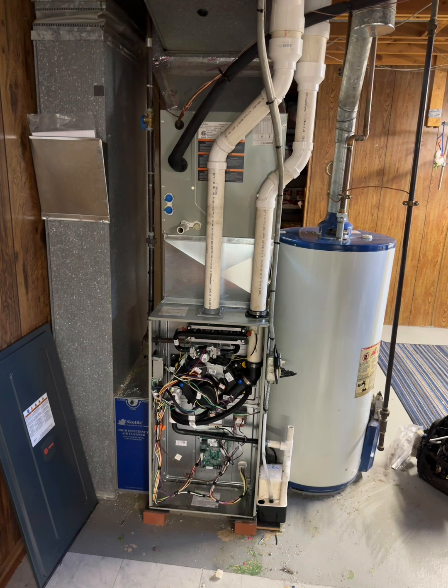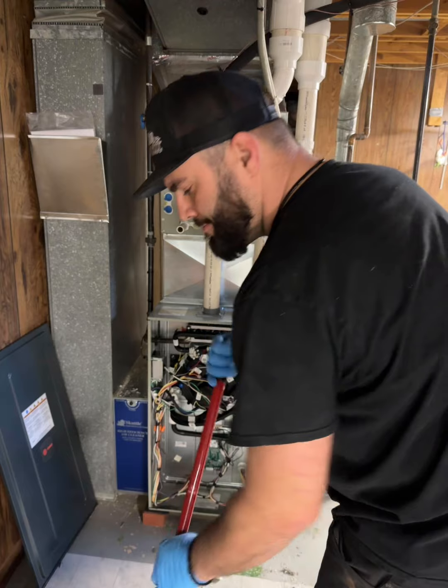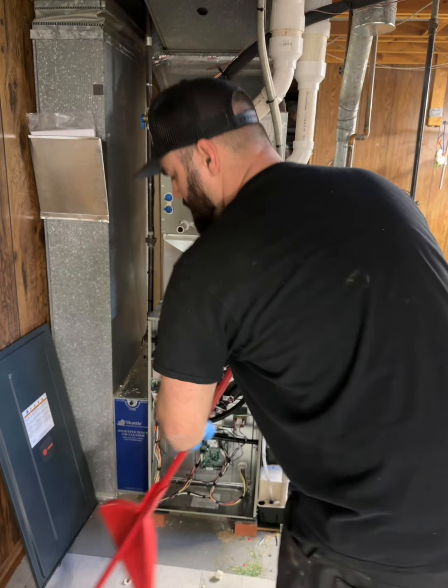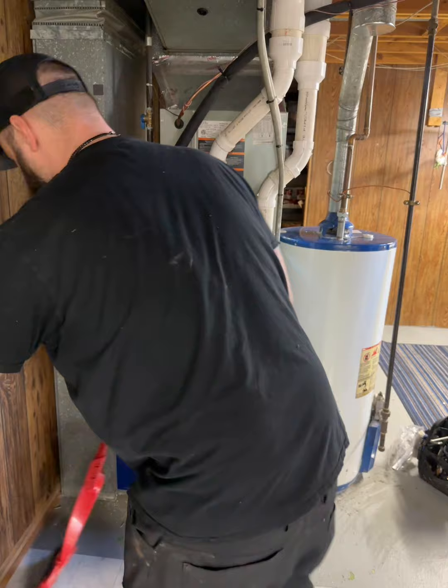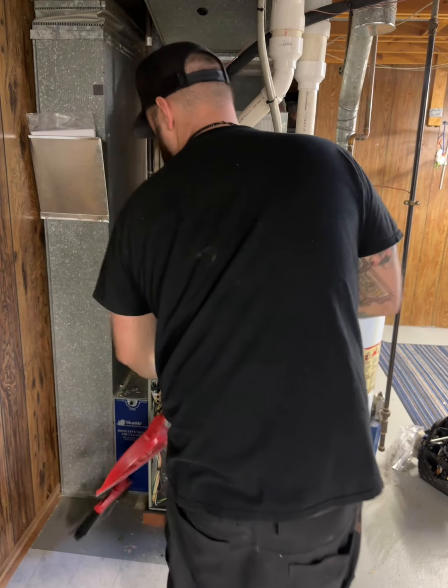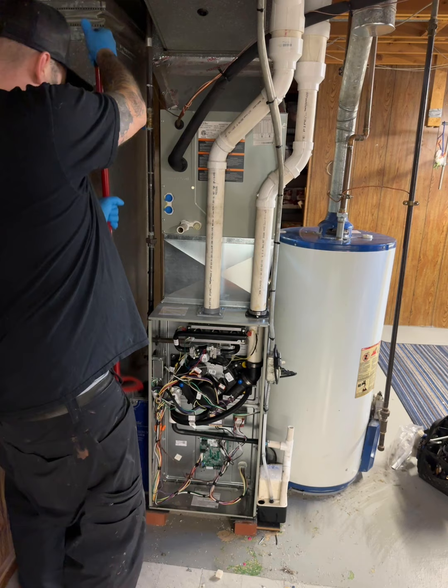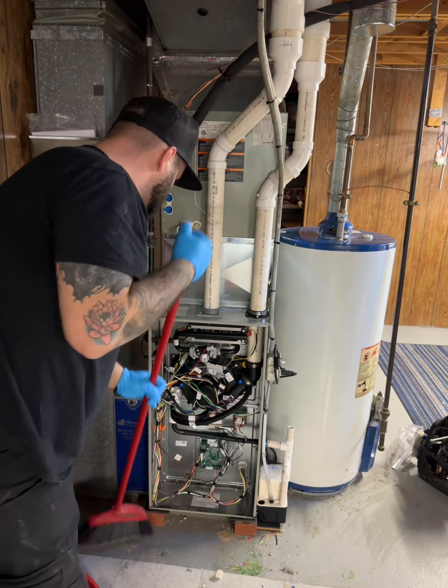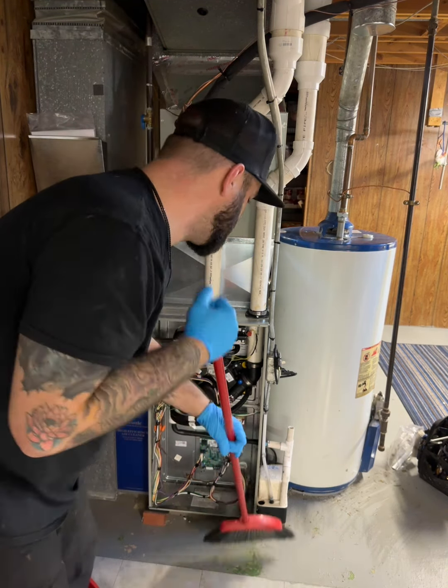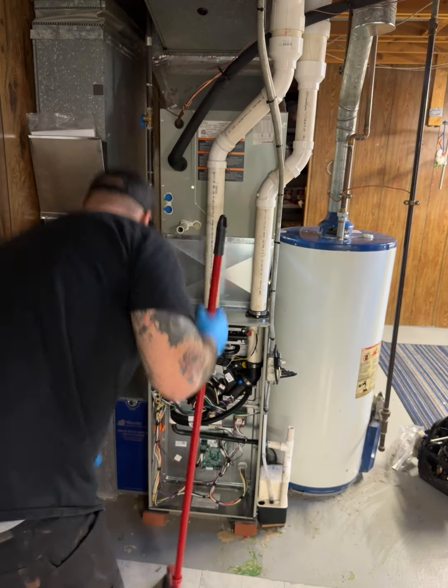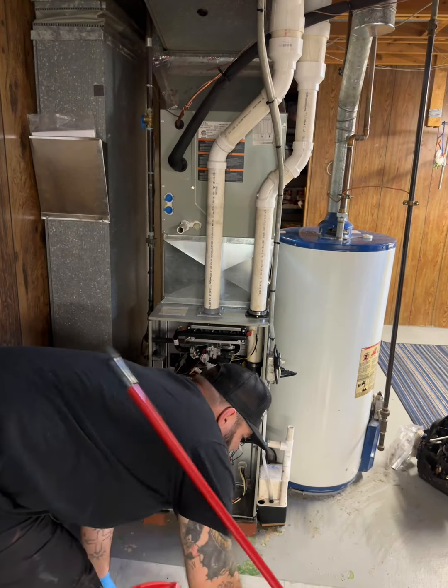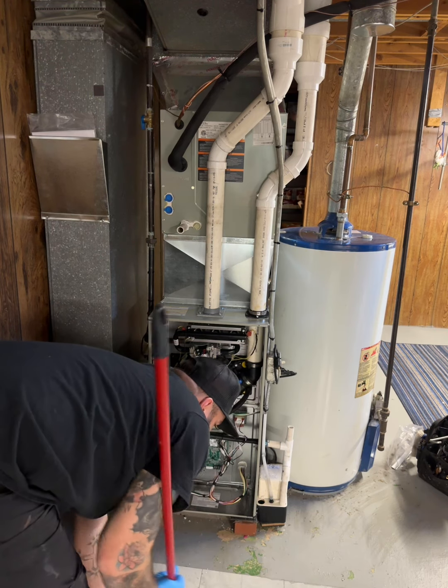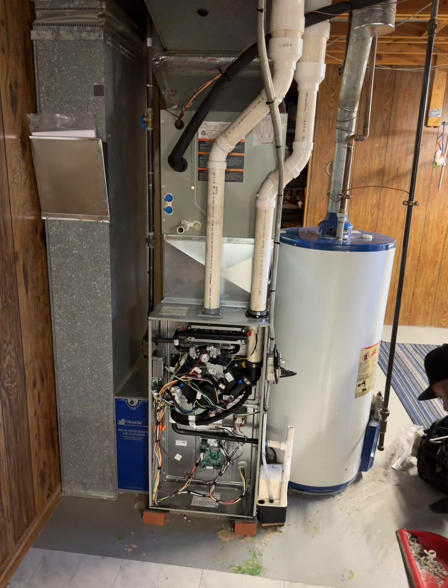On startup, we checked static pressure, made sure we were in line, and set the blower taps correctly. We also checked gas pressure and temp rise. Temp rise was great, around 35 degrees. Our gas pressure was high though, at 3.8 coming out of the factory. I did adjust it down. When I come back, I'll do a combustion test on this unit to make sure it's all dialed in as good as it can be.